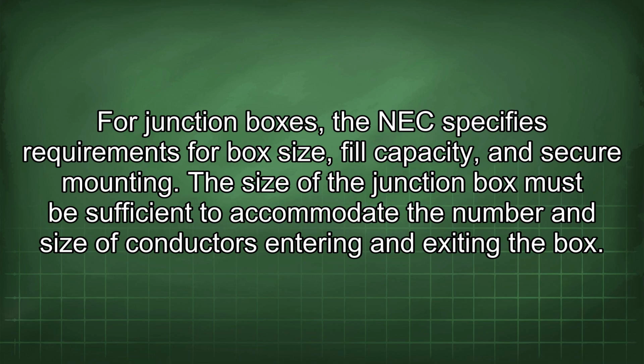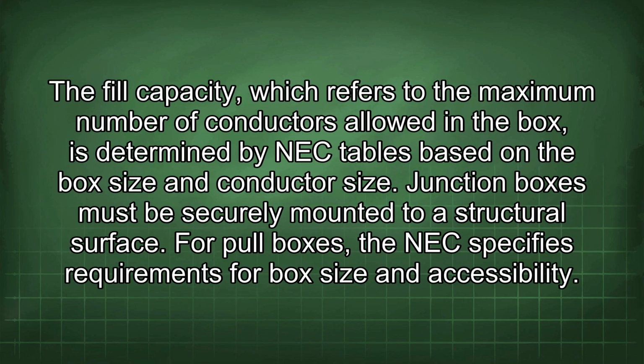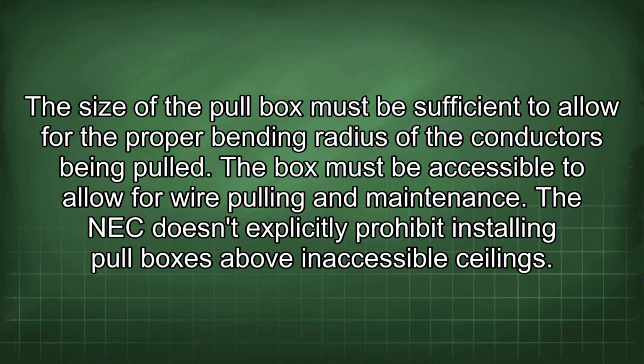The size of the junction box must be sufficient to accommodate the number and size of conductors entering and exiting the box. The fill capacity, which refers to the maximum number of conductors allowed in a box, is determined by NEC tables based on the box size and conductor size. Junction boxes must be securely mounted to a structural surface. For pull boxes, the NEC specifies requirements for box size and accessibility. The size of the pull box must be sufficient to allow for the proper bending radius of the conductors being pulled. The box must be accessible to allow for wire pulling and maintenance.